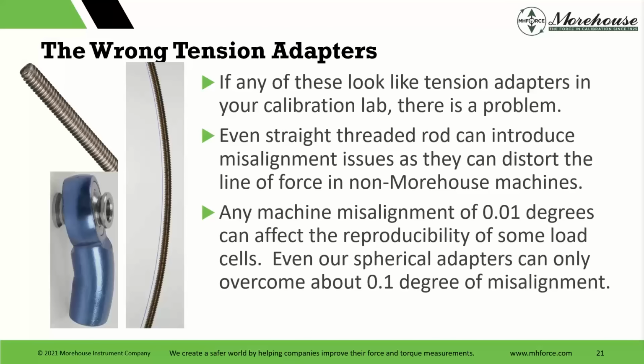This is an interesting topic. It's a little bit off of safety, though it's who's right in the design. Do we make the best force machine in the world that's plumb, level, square, rigid, so that any load cell or other instrument can be put in and have perfect repeatability, reproducibility? Or do we make a really, really good machine where we rely on the manufacturer of load cells to make sure that they're compensated for off-center loading and some misalignment built into it?